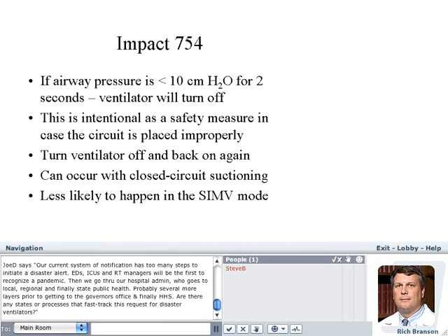So again, I want to remind you about this. If the airway pressure is below 10 for 2 seconds, the ventilator will turn off. This is a safety measure, and all you have to do is turn the switch to off and back on again. It can occur with closed circuit suctioning. And if you're going to use closed circuit suction, which I assume most of us will use, it's probably a good idea, especially if there's a contagion that's involved.